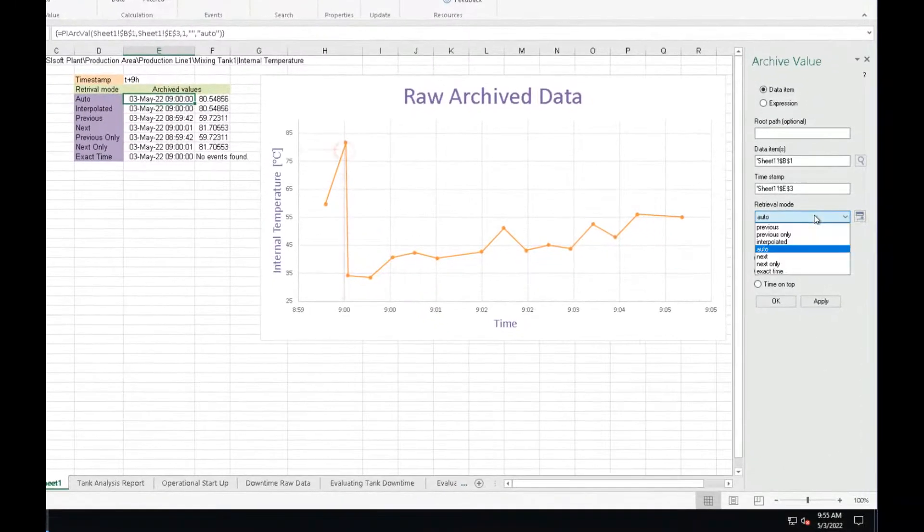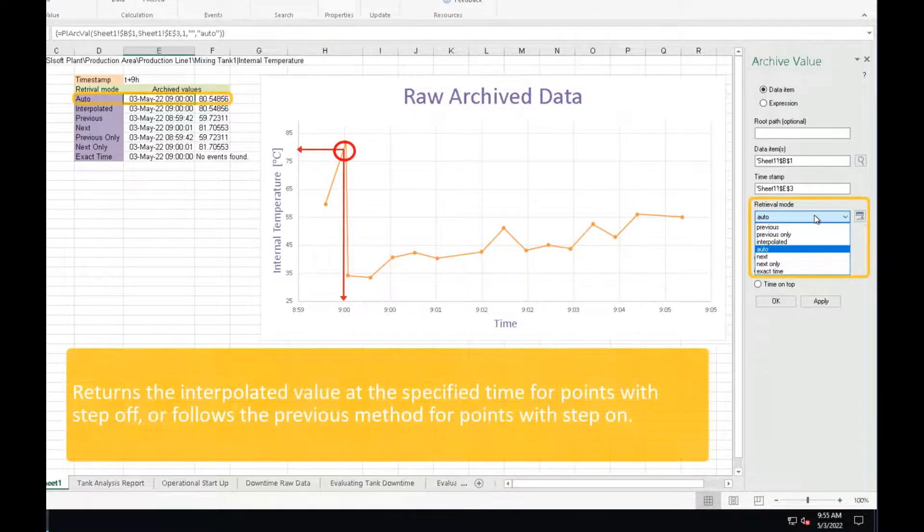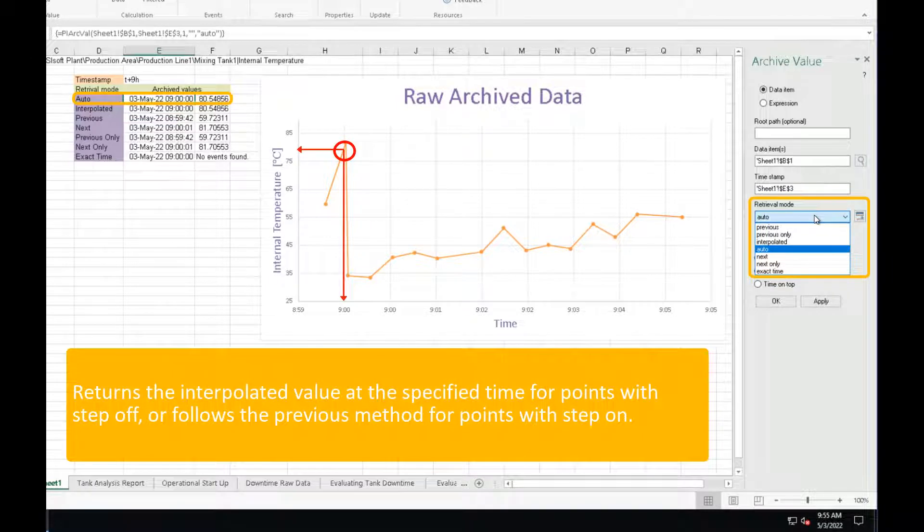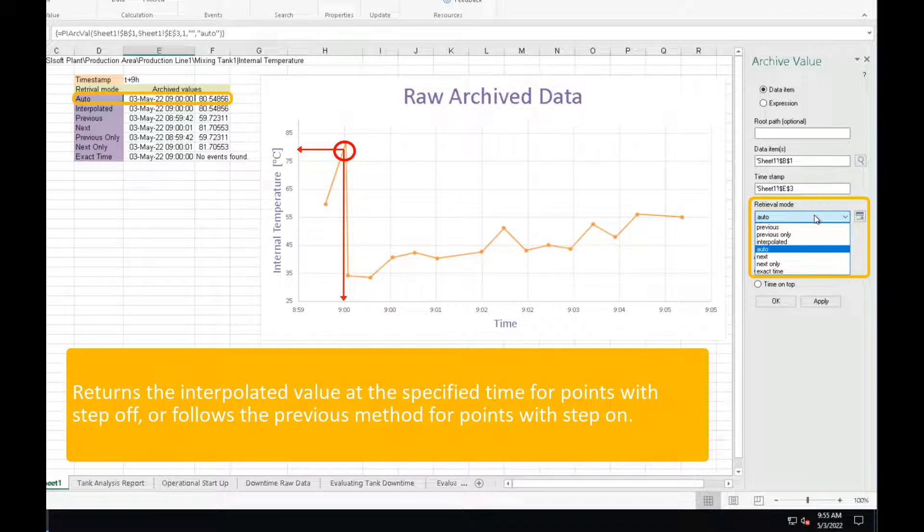The default mode is Auto. It interpolates the value at the exact timestamp provided unless the points store discrete values, such as digital state points or step points.